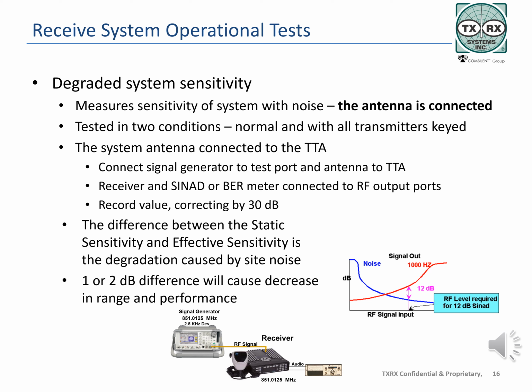The difference now will be that the antenna is connected, and noise from the outside is coming into the system. The signal generator is connected to the front panel test port on the control deck, and a receiver and SINAD or bit error rate meter are connected to the rear panel RF output port. The signal generator is set up as before, with either test signals for analog systems or the proper pattern for bit error rate testing. Adjust the signal level on the signal generator just until a 12 dB SINAD or 5% bit error rate level is reached, along with any incoming signal from the antenna determines the system's effective sensitivity.